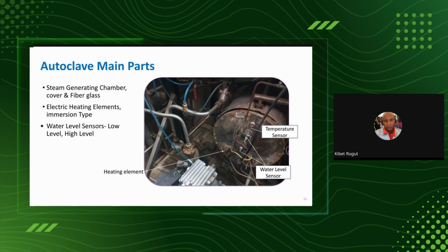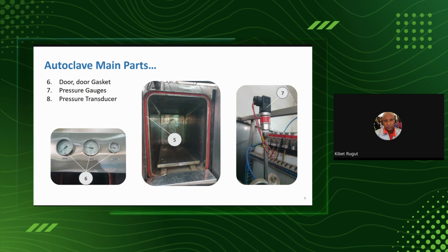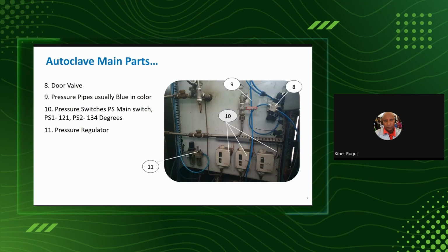And then a pressure transducer. If you find that your pressures are not recording well, it is good to know how the pressure transducers work so that you can check on them, whether electrically or pneumatically. More items that usually need to be looked at are door valves. The door cannot just simply be closed. If it is automatic, you don't have maybe a knob to rotate. You have a valve that is like a latch, and so it is pneumatically controlled.